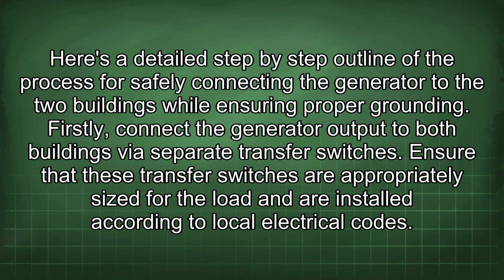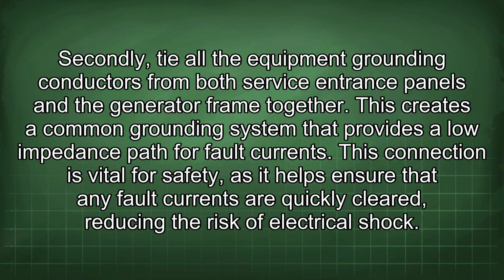Here's a detailed step-by-step outline of the process for safely connecting the generator to the two buildings while ensuring proper grounding. Firstly, connect the generator output to both buildings via separate transfer switches. Ensure that these transfer switches are appropriately sized for the load and are installed according to local electrical codes. Secondly, tie all the equipment grounding conductors from both service entrance panels and the generator frame together. This creates a common grounding system that provides a low impedance path for fault currents.